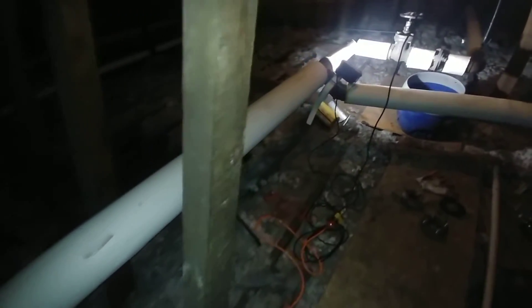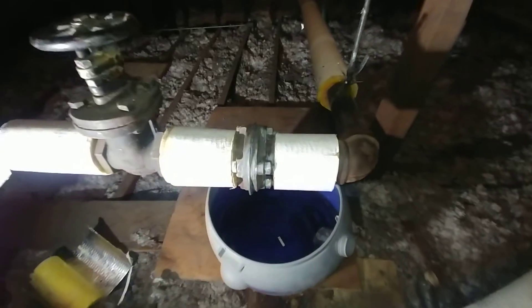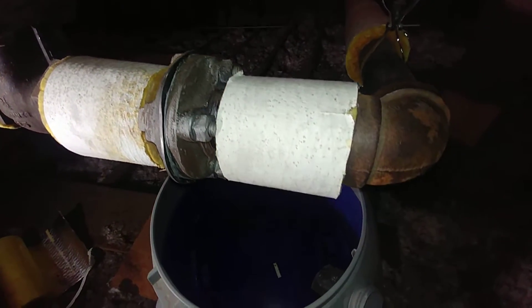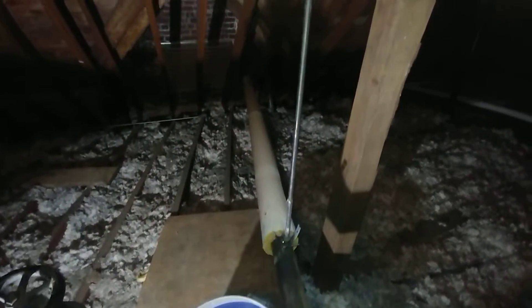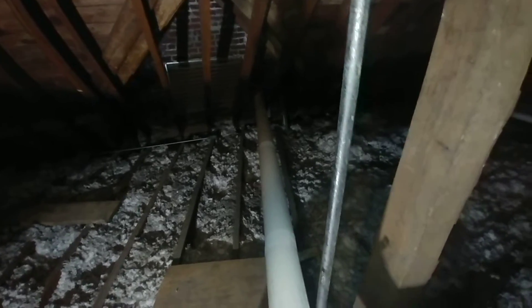There's the access way, and this is the piping. The main problem we were working on was that this flange union was leaking — there was a bucket under it to catch all the drips. You can see it's two and a half inch, and then the steam is fed down and winds up to the trap in the boiler room, right there.